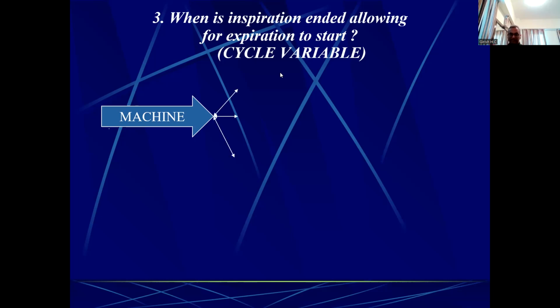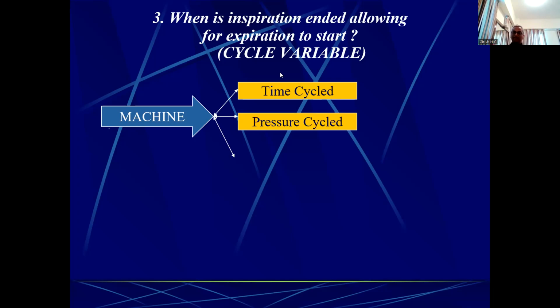In the olden day ventilators, particularly the anesthesia ventilators in the operating theater, there was something called pressure cycling, where once a certain pressure was reached, exhalation would suddenly start. We don't use that anymore. There was also volume cycling, which we used 30 years ago. For example, you give 200 cc of tidal volume, and once 200 cc is reached, the exhalation valve opens and the patient can exhale. But now most modern ventilators have time cycle. That means when you set a rate of 20 and an I time of 1 second, after 1 second of inspiration and 2 seconds of exhalation, every 3 seconds the exhalation valve opens to let the patient exhale.